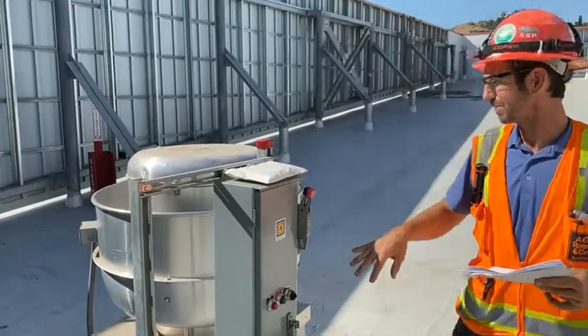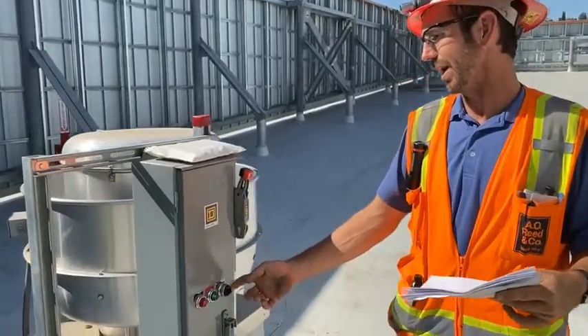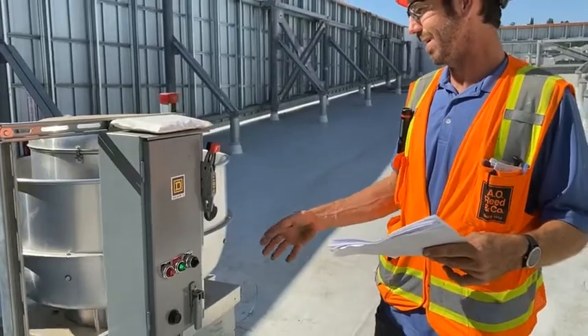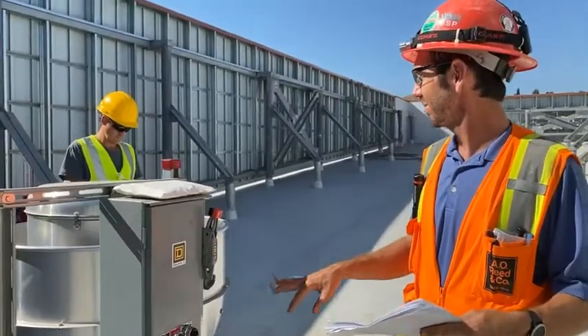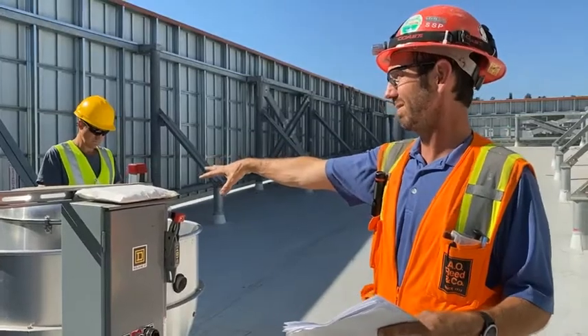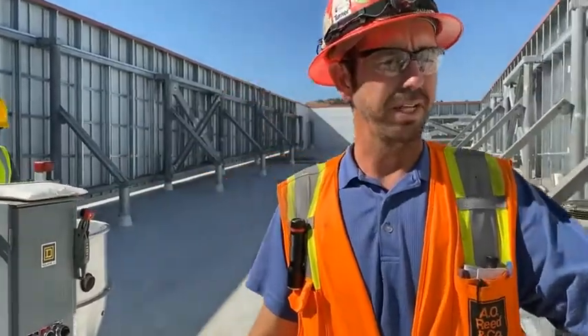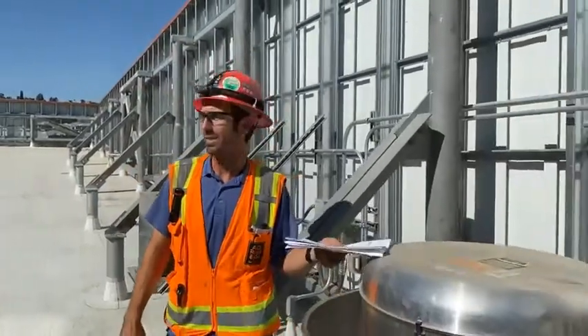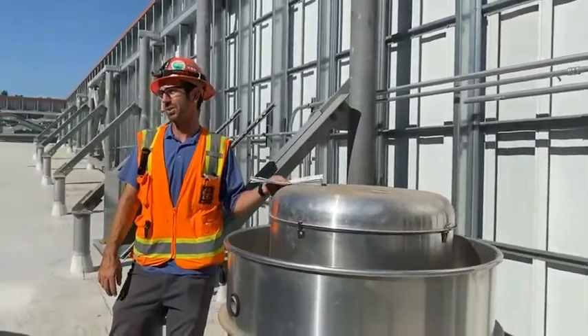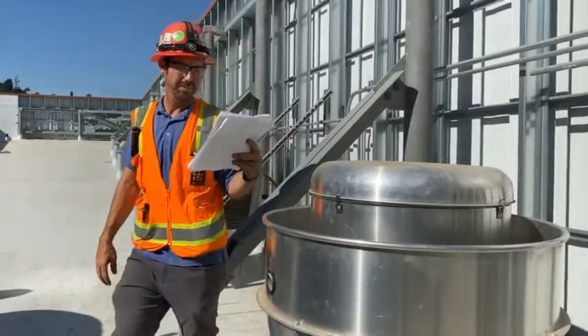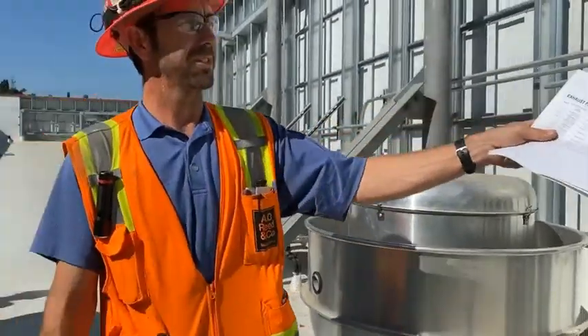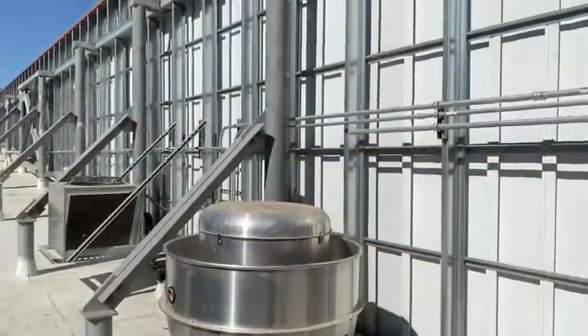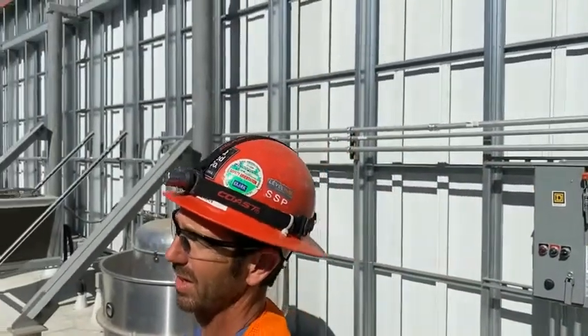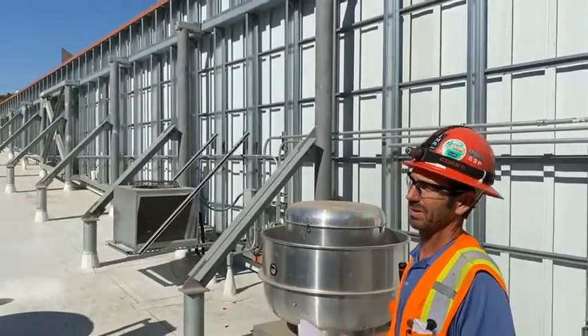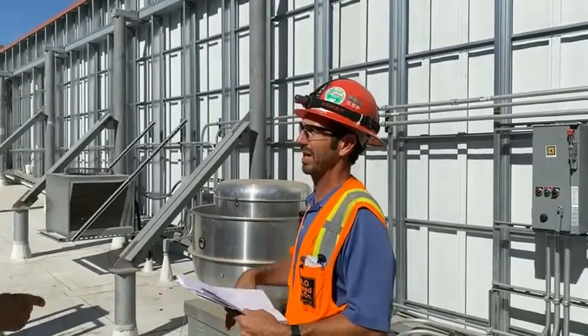Same starter, same controls, keep it in auto, but auto and off doesn't really matter. It's still gonna come on through the Ansul system. Belt driven, greasable bearings, okay? EF4D, same thing. 4D is the pizza oven, okay? Greasable bearings, belt driven. Same thing with the starter right here. As far as maintenance, it's the same maintenance as the other fans. Same requirement, right? Check belts quarterly, minimal oil, and the same grease that I showed you guys.